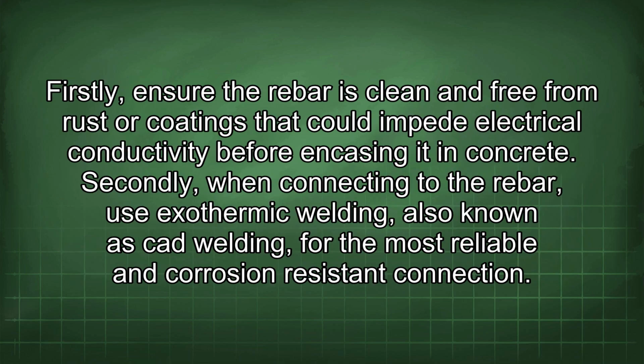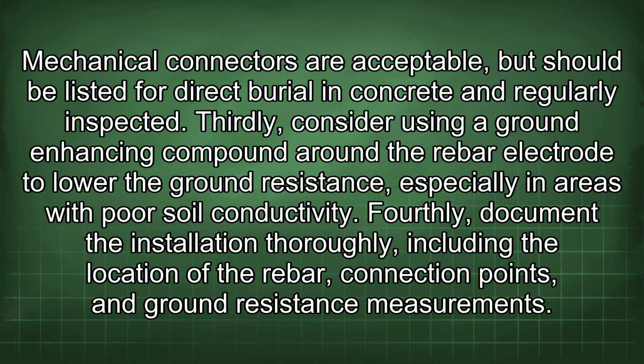Firstly, ensure the rebar is clean and free from rust or coatings that could impede electrical conductivity before encasing it in concrete. Secondly, when connecting to the rebar, use exothermic welding, also known as CAD welding, for the most reliable and corrosion-resistant connection. Mechanical connectors are acceptable, but should be listed for direct burial in concrete and regularly inspected. Thirdly, consider using a ground-enhancing compound around the rebar electrode to lower the ground resistance, especially in areas with poor soil conductivity.